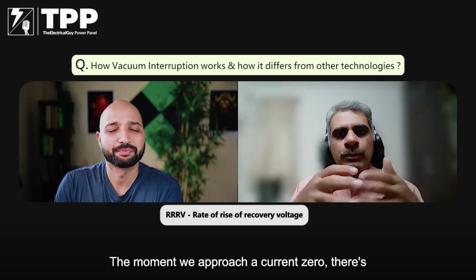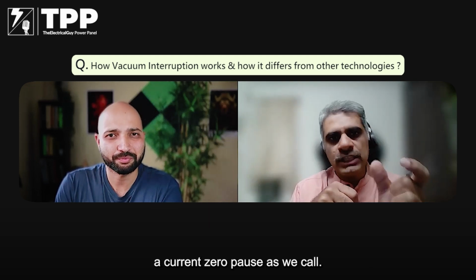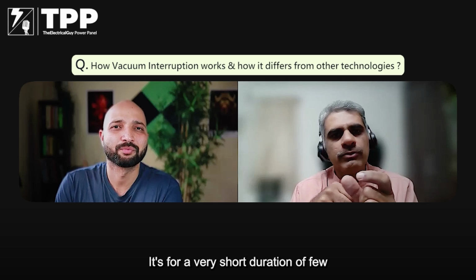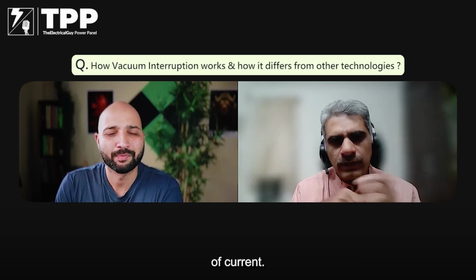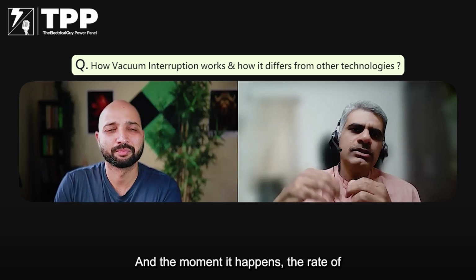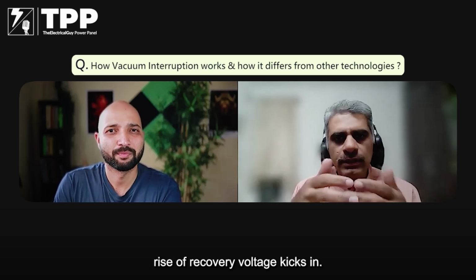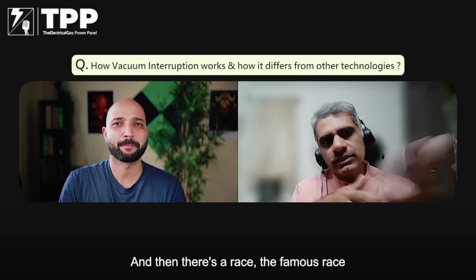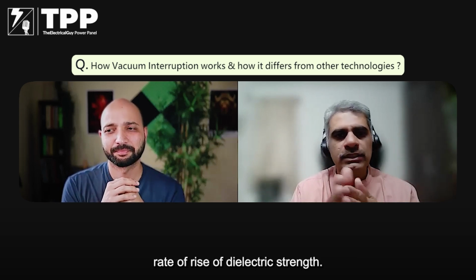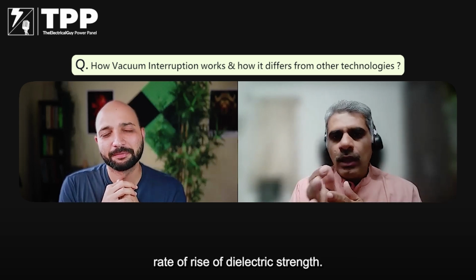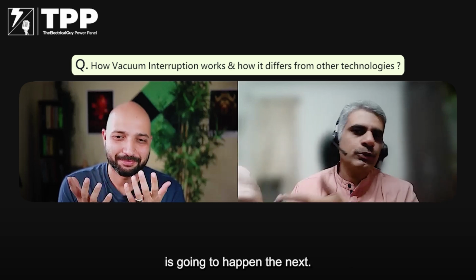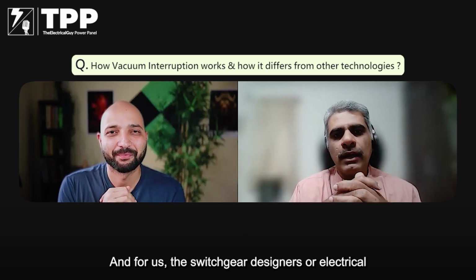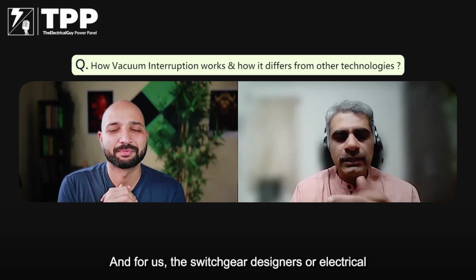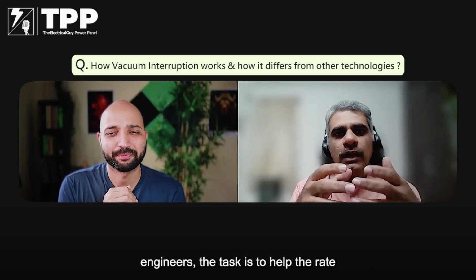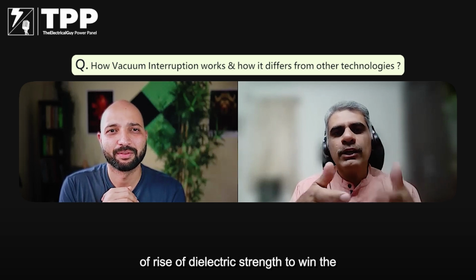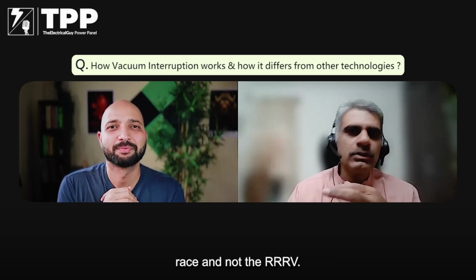The moment we approach a current zero, there's a current zero pause, as we call it. It's for a very short duration of a few nanoseconds, but there's a pause in the value of current. And the moment it happens, the rate of rise of recovery voltage kicks in. And then there's a race, the famous race between rate of rise of recovery voltage and rate of rise of dielectric strength. The one who wins the race decides what is going to happen next. For us, the switchgear designers or electrical engineers, the task is to help the rate of rise of dielectric strength win the race and not the RRRV.